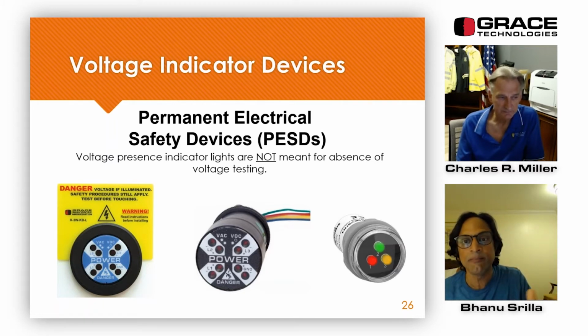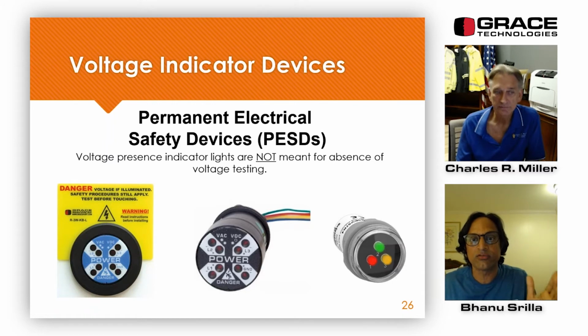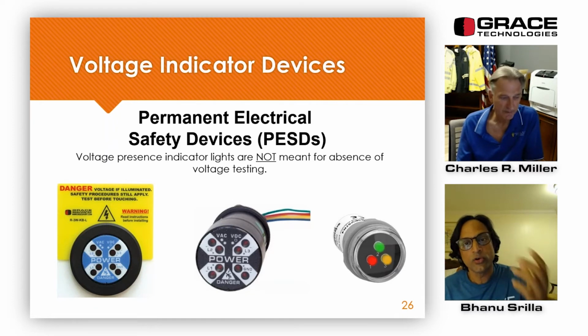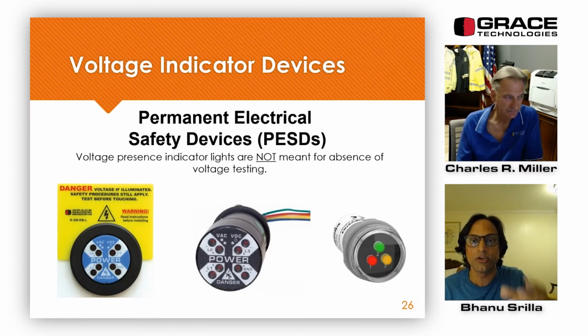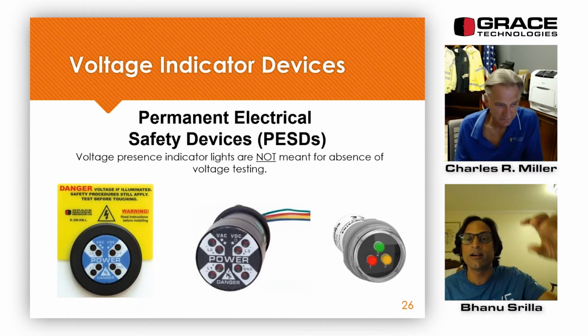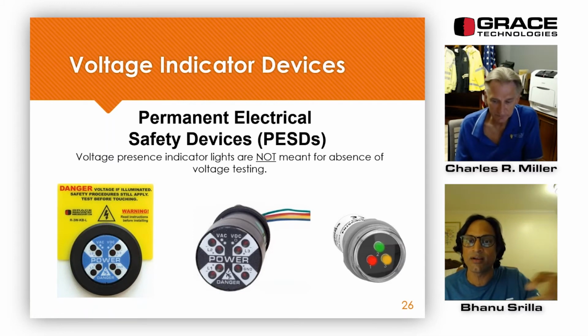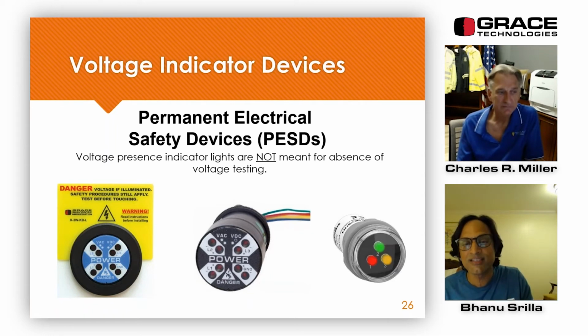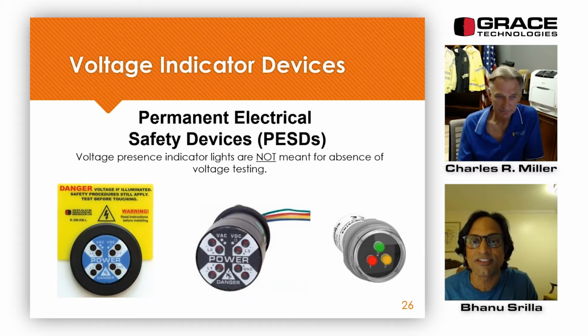For example, there are disconnect switches where you have a visible blade, where you can see through the window the status of the disconnect switch. If you don't have that in your legacy equipment, you can install these devices, where if the blade got stuck, when these devices are wired, this will give you a flashing light outside the door. And again, these devices are meant only for task qualified persons or unqualified persons per 70E definition. This is not meant for absence of voltage testing. That's why I want to make it very clear.